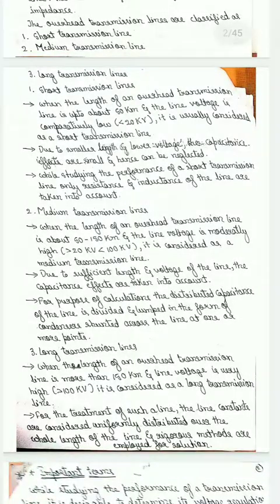Medium transmission line: when the length of an overhead transmission line is about 50 to 150 kilometers and the line voltage is moderately high, it is considered a medium transmission line. Due to sufficient length and voltage of the line, the capacitance effects are taken into account. For calculation, the distributed capacitance of the line is divided and lumped in the form of condensers shunted across the line at one or more points.